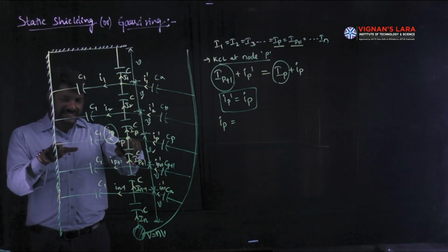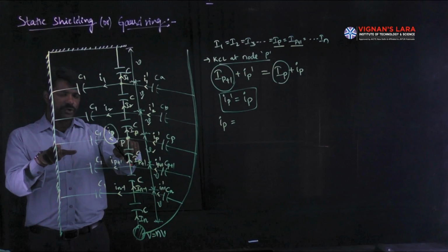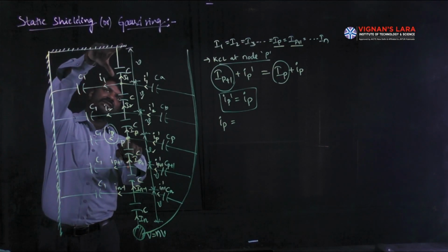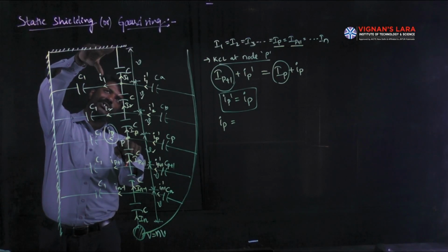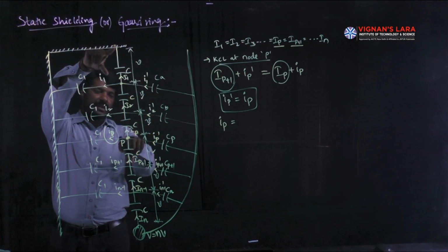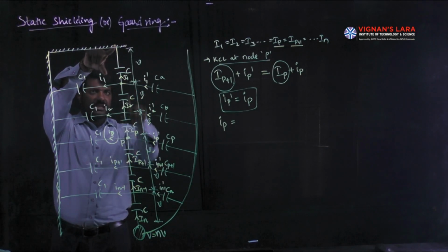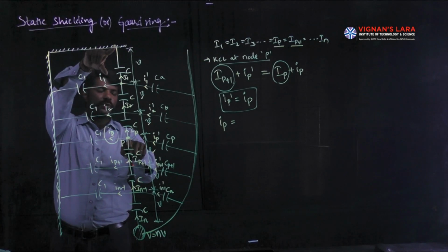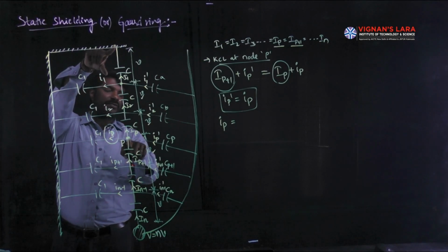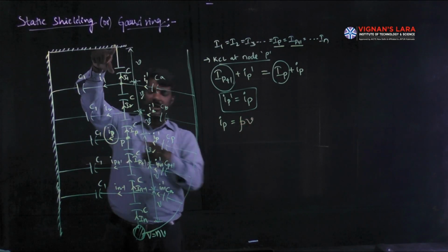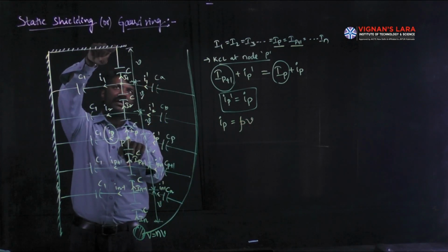The voltage existing between them should be known first. The same earth is maintained here to the cross arm. So from this node to this cross arm, the voltage available is P number of units, each unit having a voltage of V volts. Then at this node we can observe PV as a voltage. Therefore, P into V is the voltage between this node and cross arm.